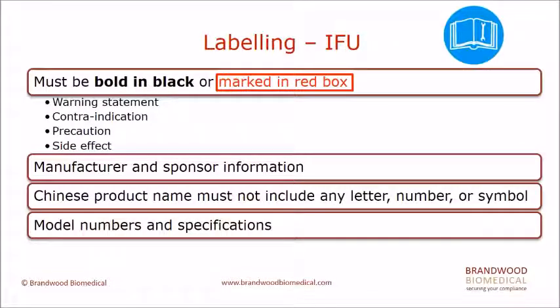The manufacturer and sponsor information must be included in the Chinese IFU. The Chinese product name must not include any letter, number, or symbol. Model numbers and specifications must be included at the end of the Chinese IFU. Those are the key requirements. We would suggest complying with them to avoid delay when submitting the application to Taiwan FDA. Any minor updates can be done during the reviewing process upon request.